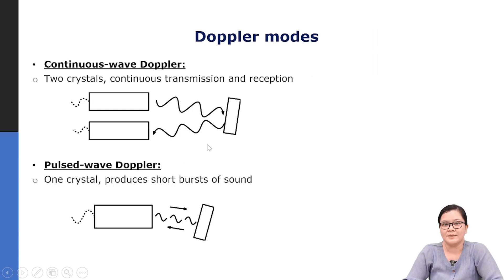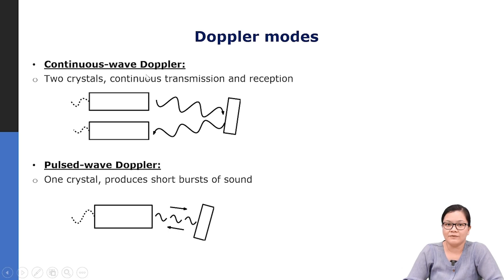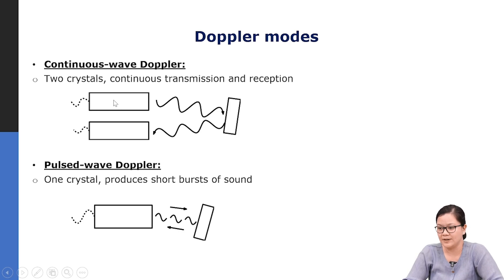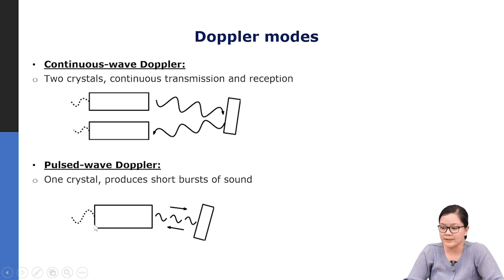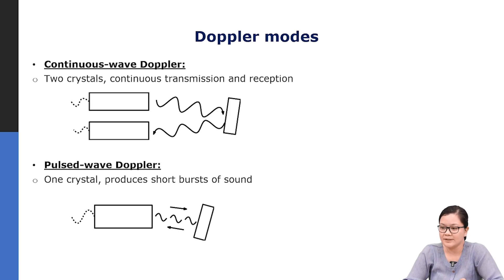Two Doppler modes are commonly used in ultrasound. Continuous wave (CW) Doppler uses two piezoelectric elements — one for continuous transmission and one for continuous reception of echo signals from the blood. Pulsed wave Doppler uses one crystal producing short bursts of ultrasound. Both modes are frequently used in clinical ultrasound.